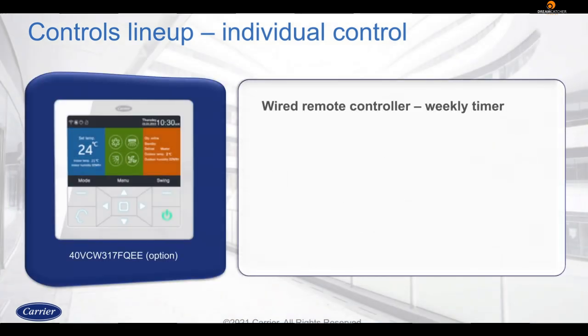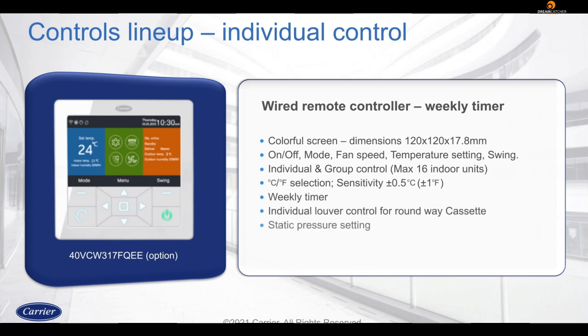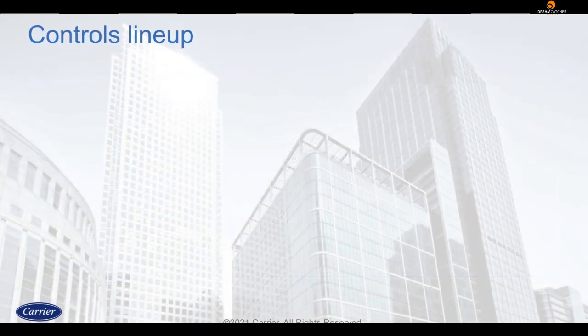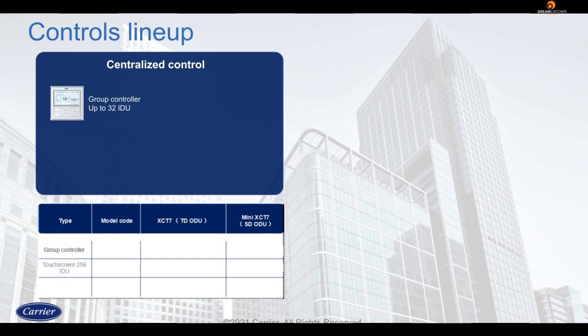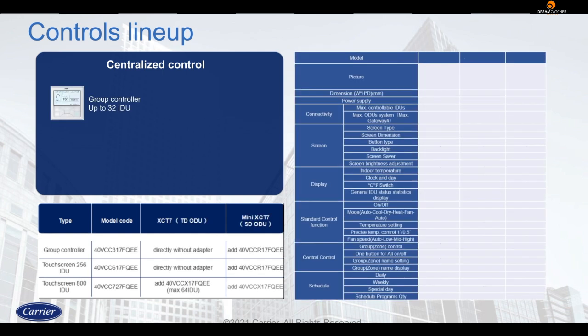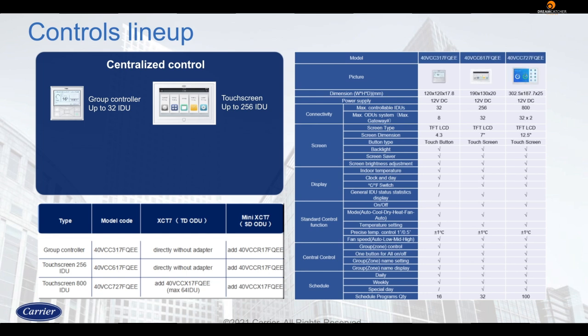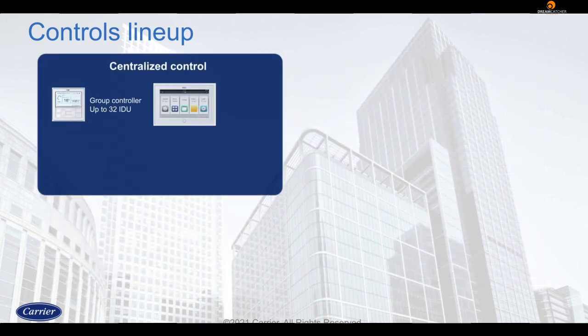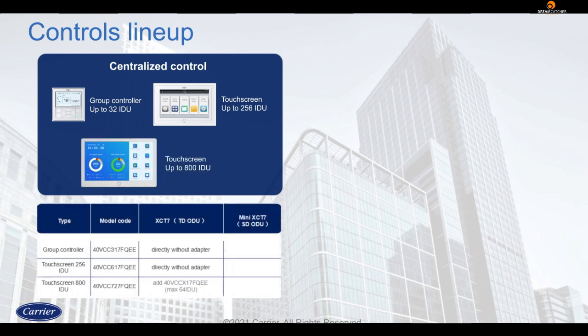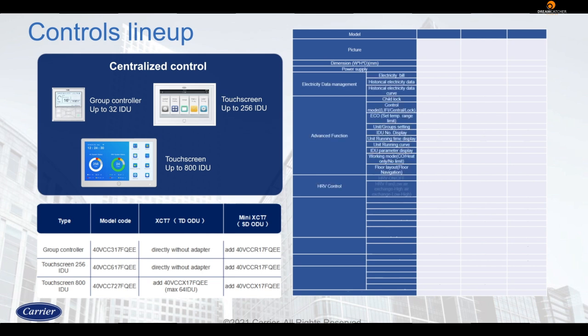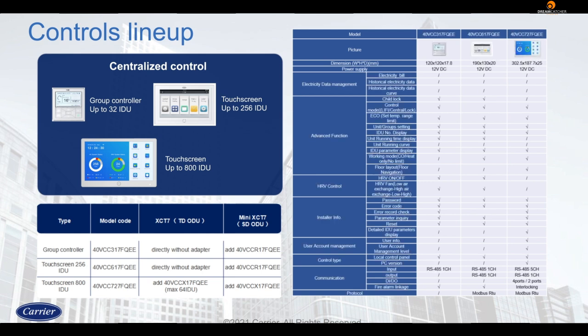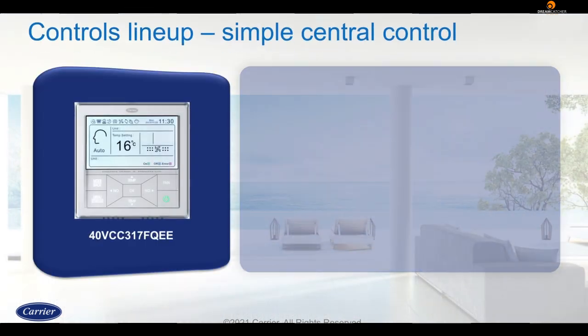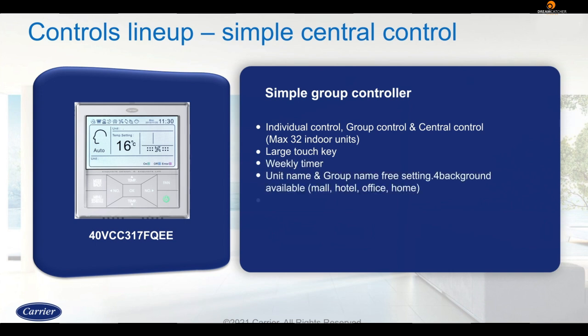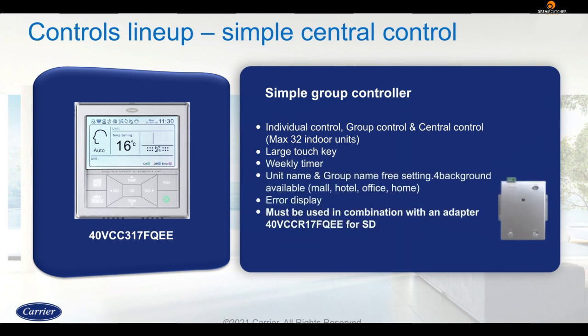The XCT7 also comes with a wired remote controller with a weekly timer and colorful screen. It can control individual and groups of indoor units, up to a maximum of 16. The centralized controls for the XCT7 come with a group controller that can connect with 32 IDUs, a touchscreen controller that can connect with 256 IDUs, and a touchscreen that can connect with 800 IDUs. The simple group controller can control up to 32 units and is suitable for mall, hotel, office, or even home application.